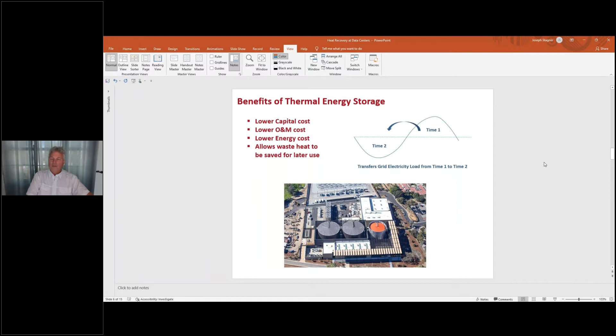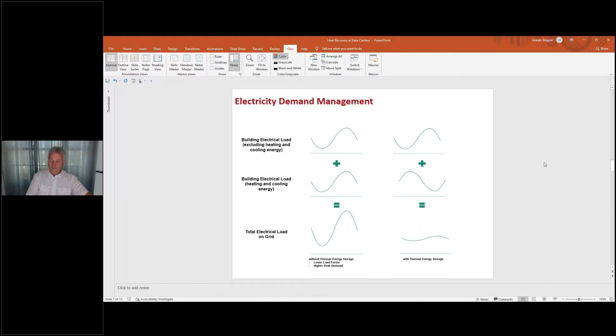This just shows an example. If you don't use thermal storage, you're compounding your sinusoidal demand on the grid with how electricity is used at your data center and how heat is generated, requiring additional electricity concurrently for cooling. You can either be on the left column and make your peak worse and worse, or use thermal storage on the right to flip the equation and greatly flatten your electrical demand and cost.